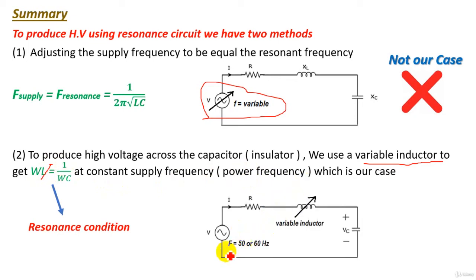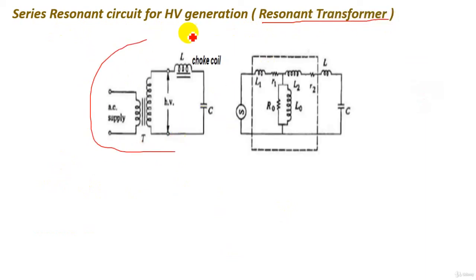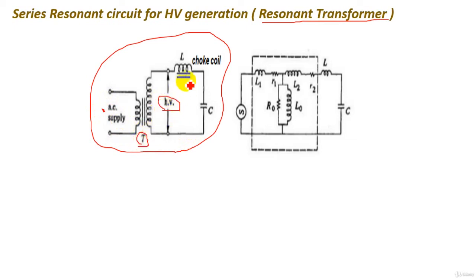This is the equivalent circuit. We have a constant supply frequency of 50 or 60 Hz and a variable inductor. This value of inductor is designed and adjusted to get ωL equal 1/ωC. The series resonant circuit for high-voltage generation is also called a resonant transformer. We have an AC supply of 220 volts, a high-voltage transformer, a choke coil which is a variable inductor to adjust its value to make resonance, and a capacitor C representing the insulator in the high-voltage lab.